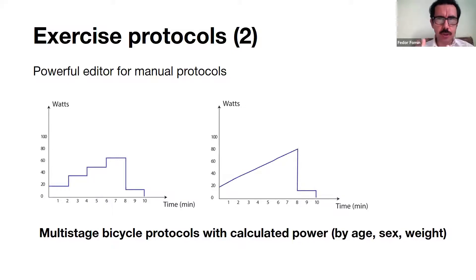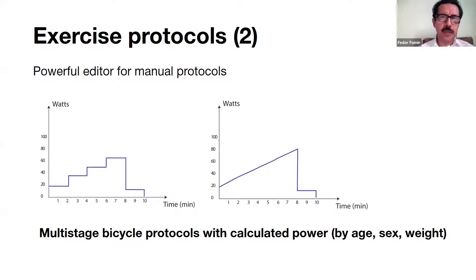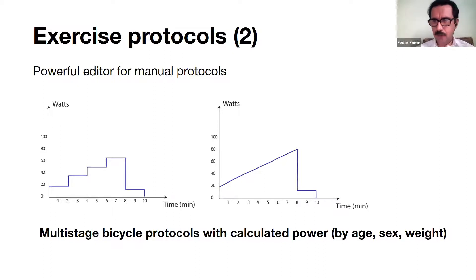Why is that important? In two cases: when you deal with athletes and when you deal with children. There are protocols that require workload in watts per kilogram of body weight. If you have persons weighing 45 kg or 65 kg and you set up a protocol where the first stage is 0.5 watts per kilo, the next one watt per kilo, and so on — the system will automatically recalculate and perform this step-by-step exercise according to the formula. It's very interesting, but it works only for bicycle.